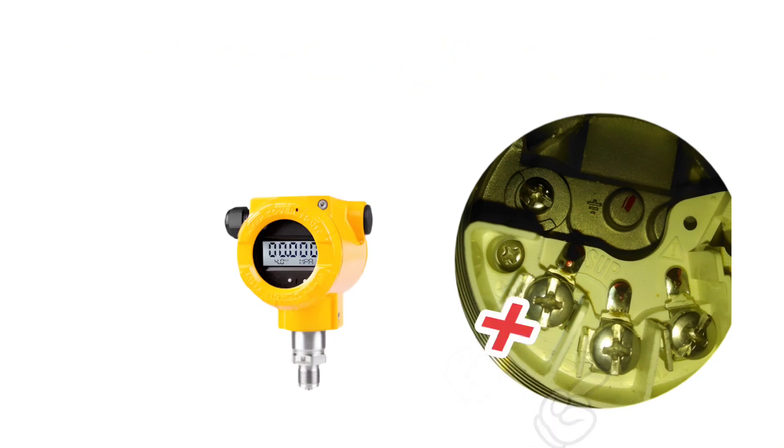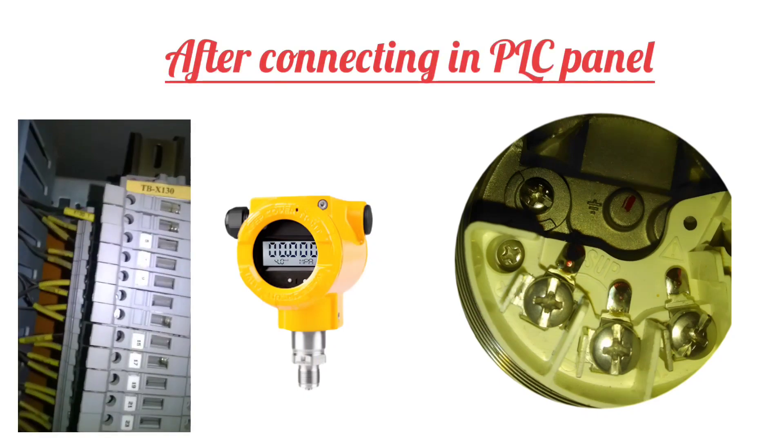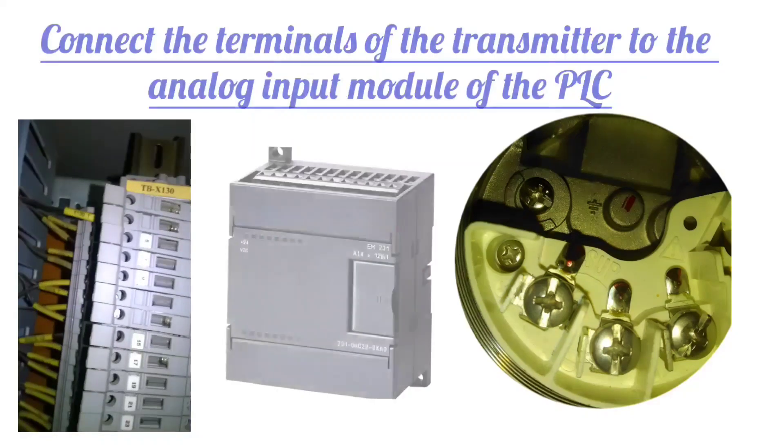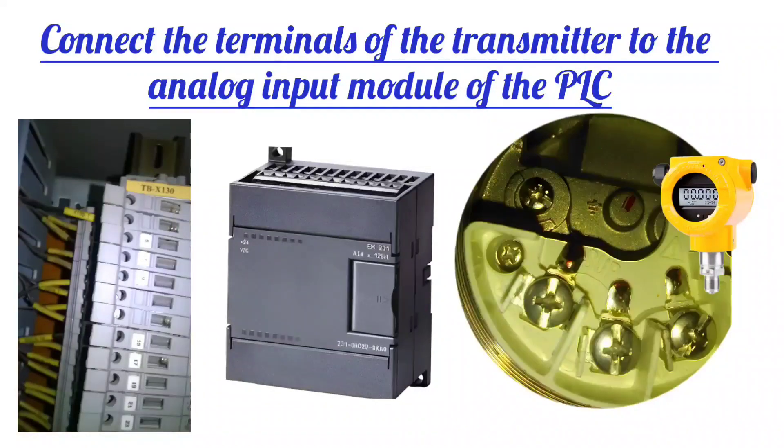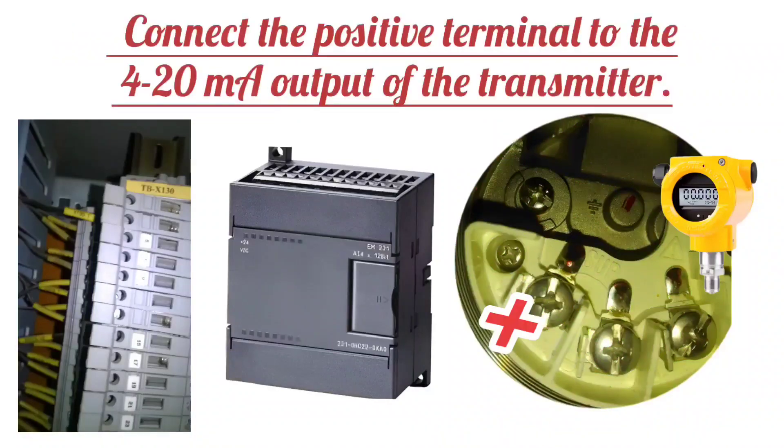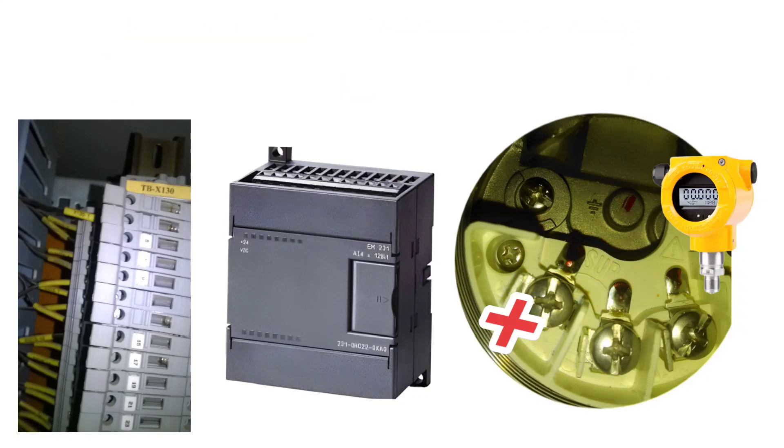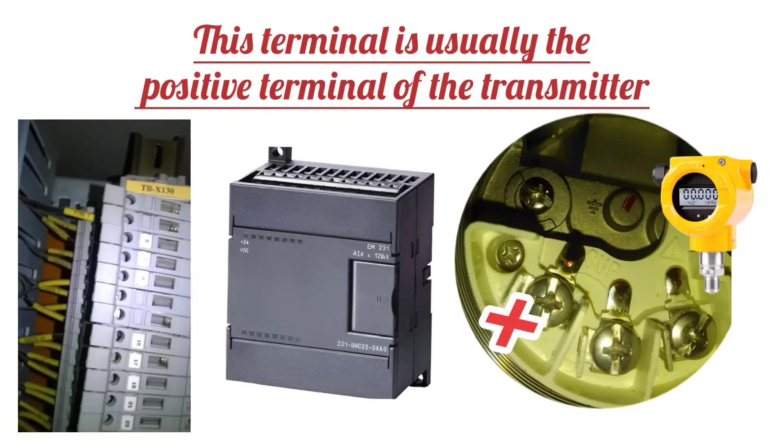After connecting in PLC panel, connect the terminals of the transmitter to the analog input module of the PLC. Connect the positive terminal to the 4 to 20 milliampere output of the transmitter. This terminal is usually the positive terminal of the transmitter.